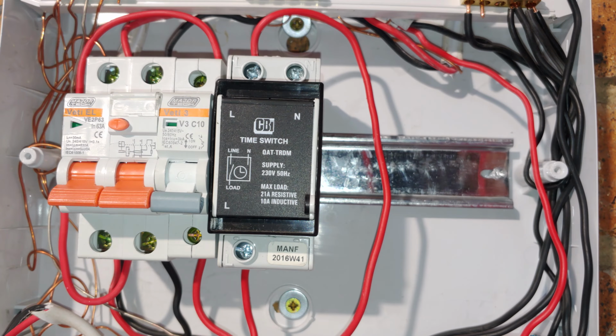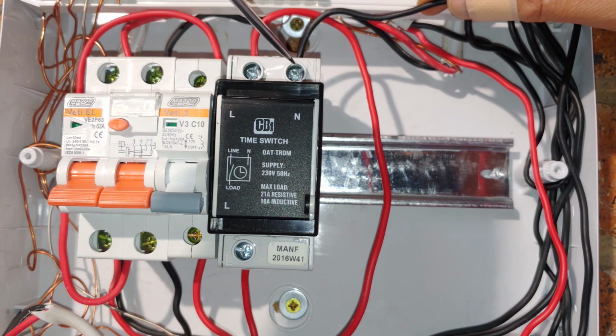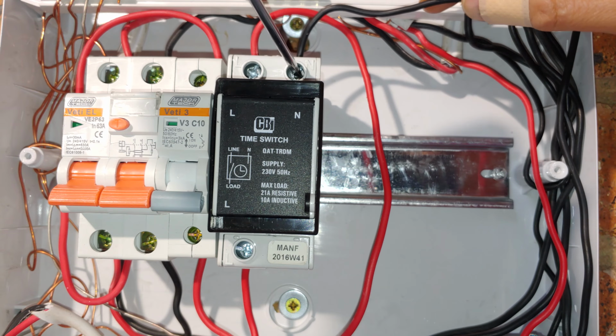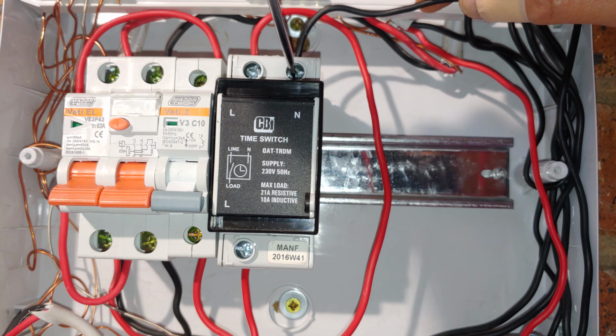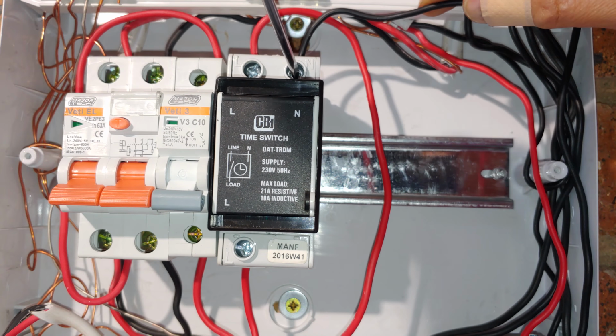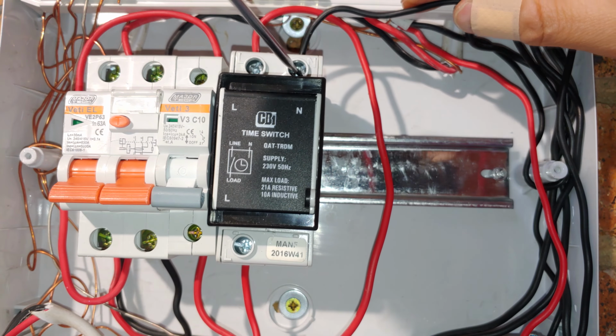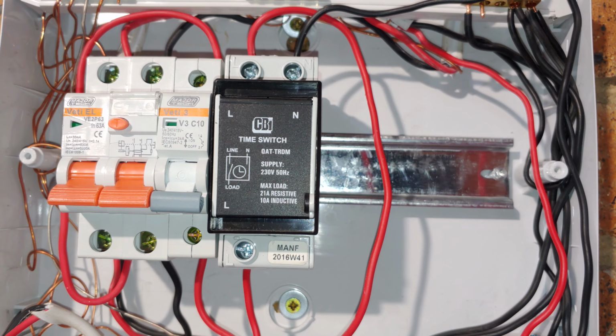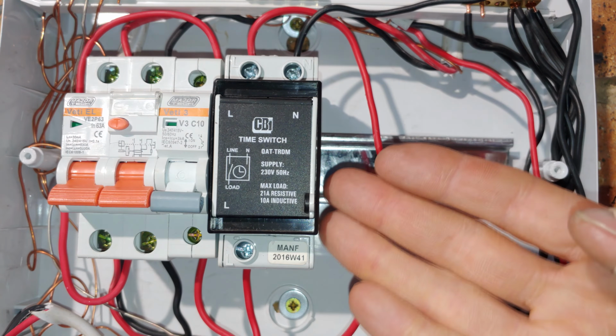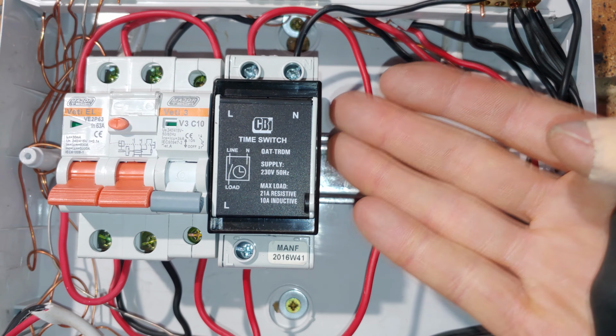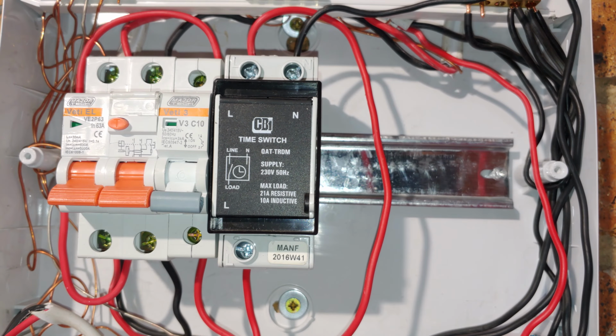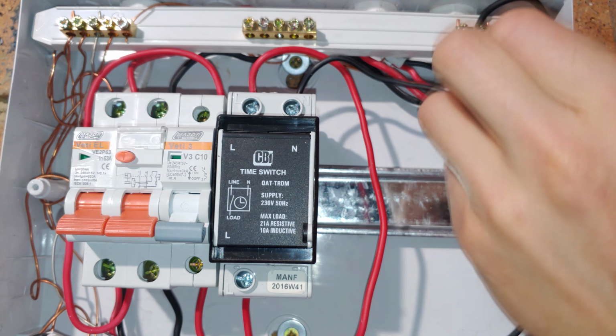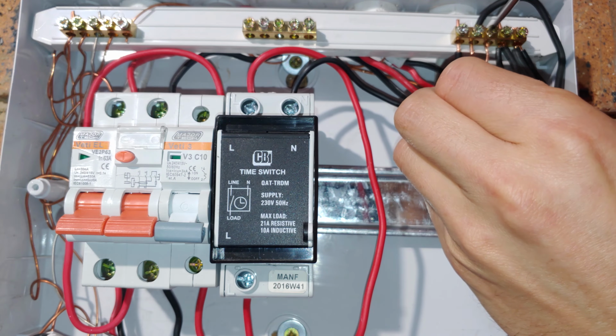Now the final step is just to connect the neutral. The reason why it requires a neutral is this timer switch requires a little bit of current just to power itself, because it's got a little super capacitor in there to store the programming when the power goes off. You can think of it like a battery that has to be charged, and this thing needs its own neutral. So I'm just connecting it to the neutral rail at the top, finding an available slot.